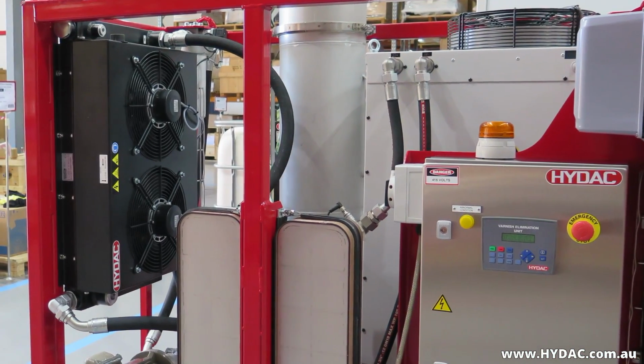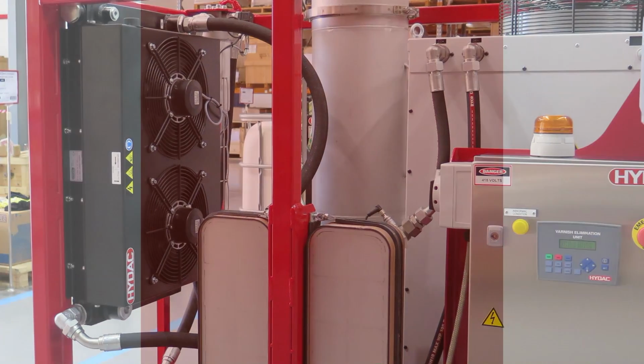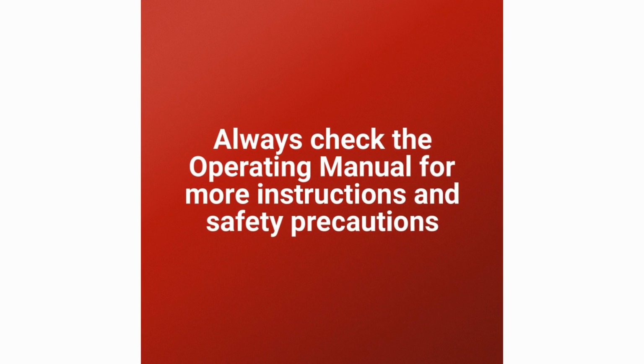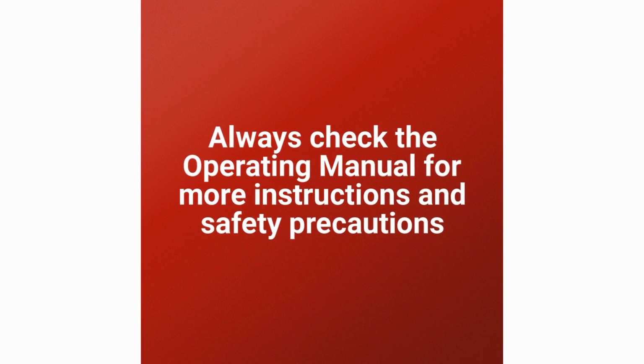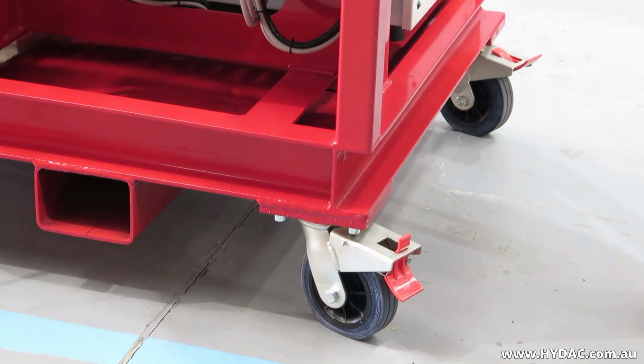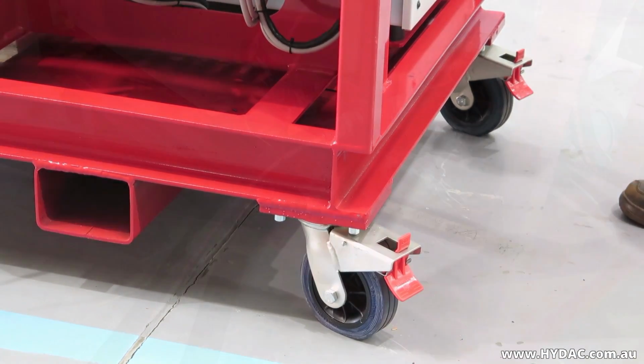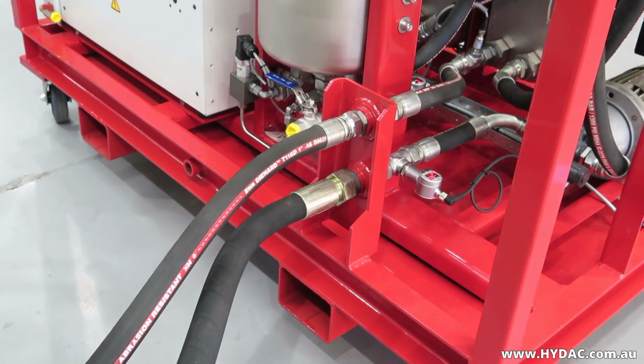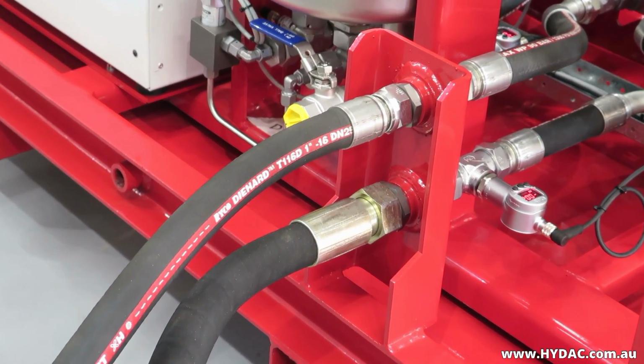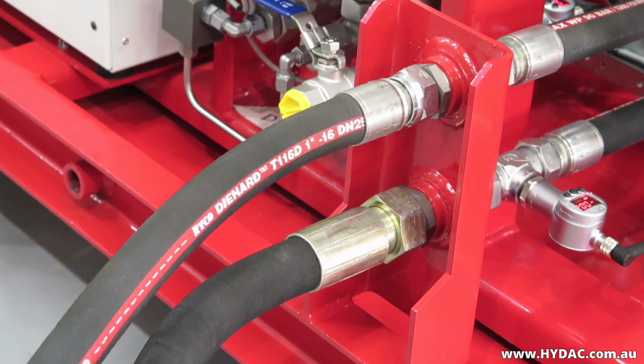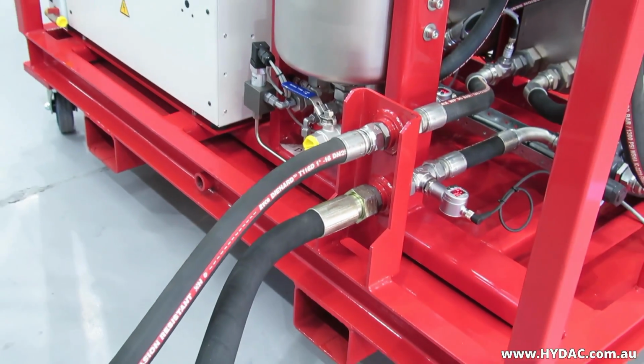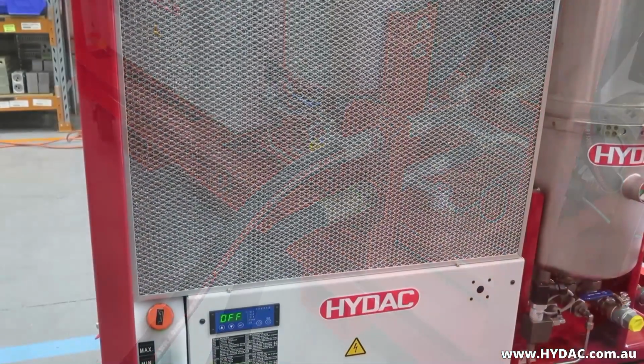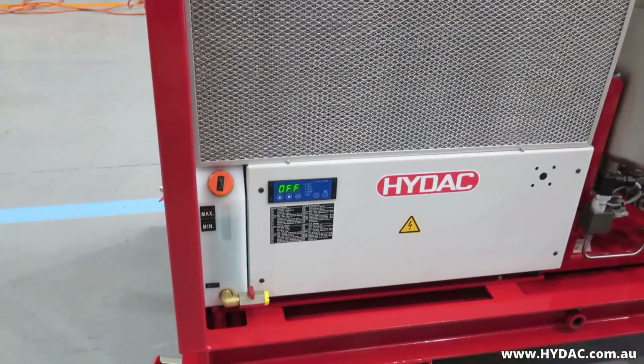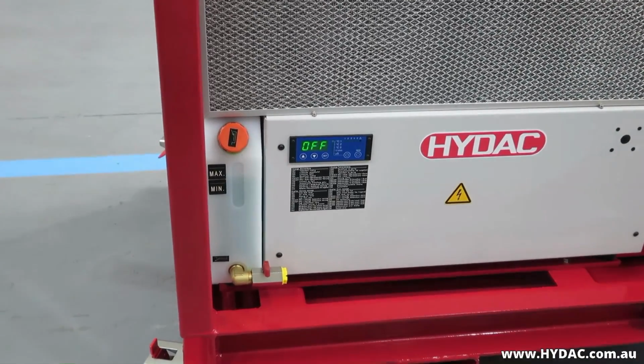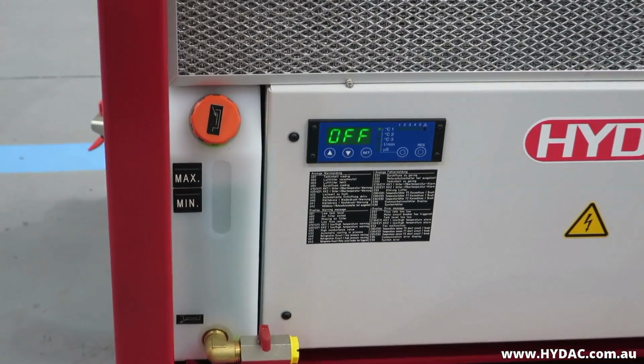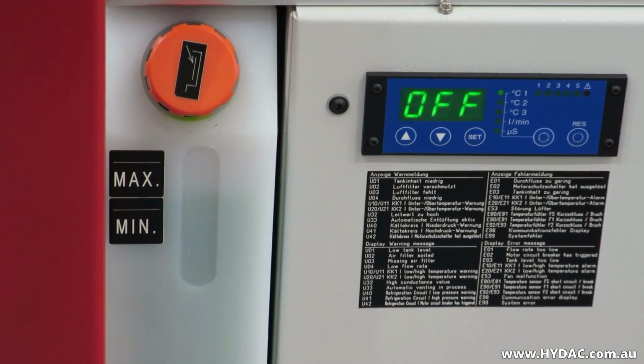Prior to starting the system, do the following, remembering to always check the operating manual for more instructions and safety precautions. Position the unit in place and apply the wheel brakes. Connect the hoses to the inlet and outlet ports. It's important to only use the hoses that are supplied with the unit, as these are designed specifically for the application. Make sure that there is no obstruction in the front of, around, or above the chiller or the air blast cooler. Check the chiller tank level and top up.